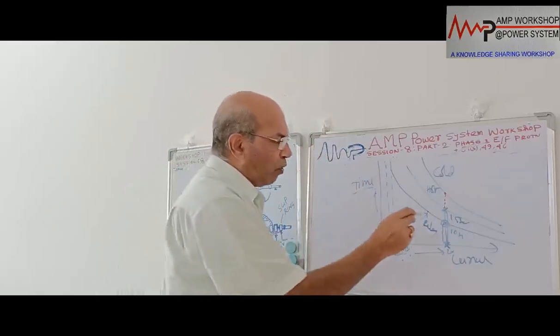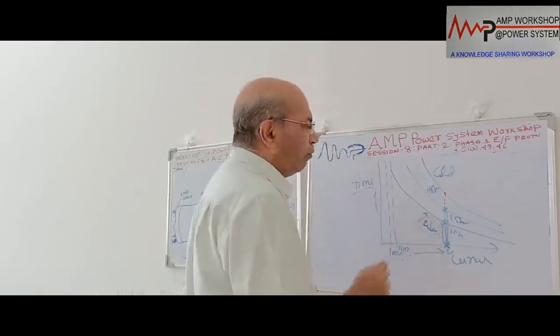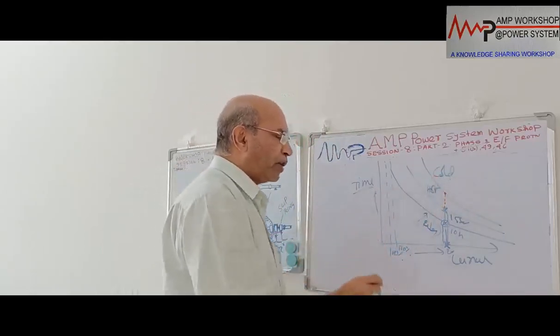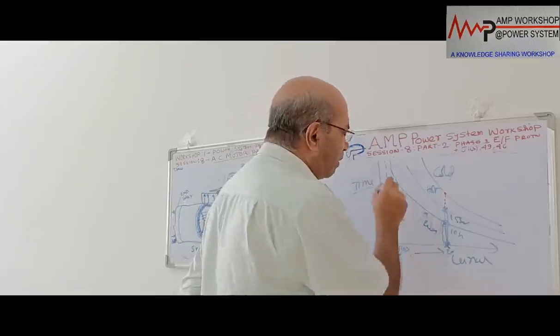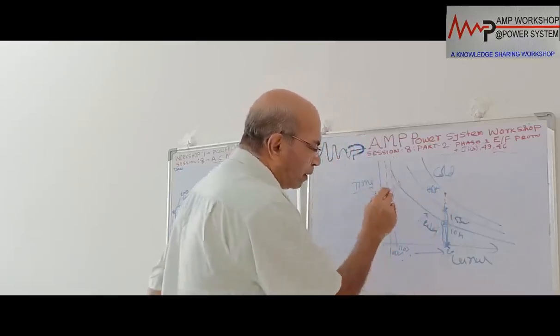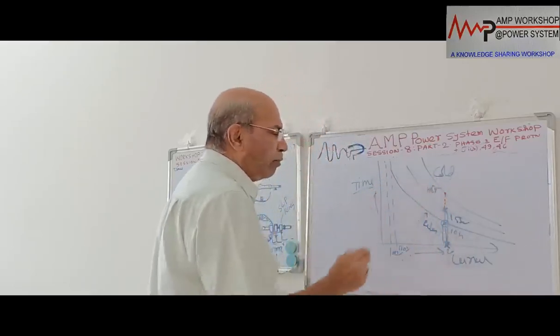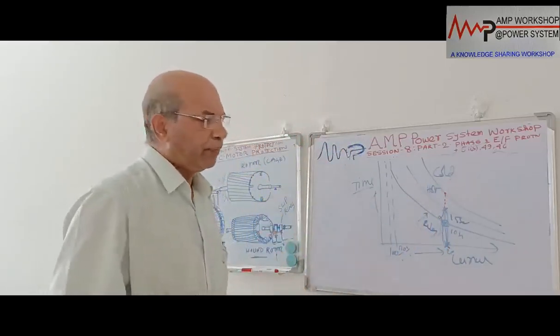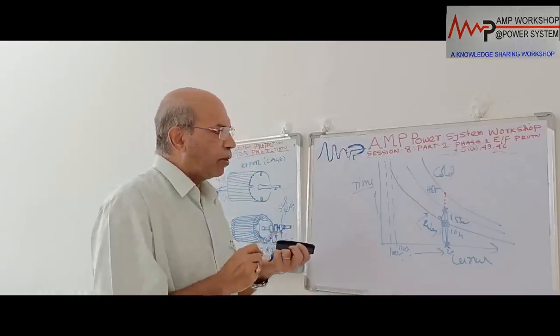So we have to coordinate the motor protection device curve with respect to the cold and hot curves. In the case of overload protection, the motor protection curve must be below the motor curve, with an adequate difference between the two, so that the motor can be protected. That is for the motor overcurrent protection.